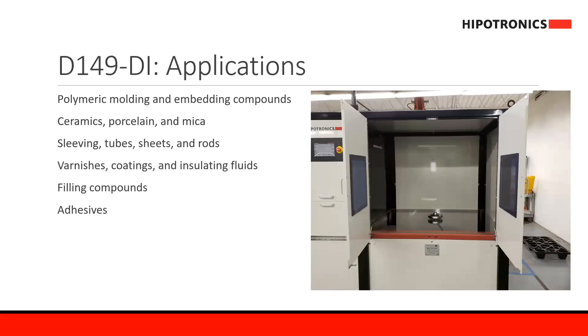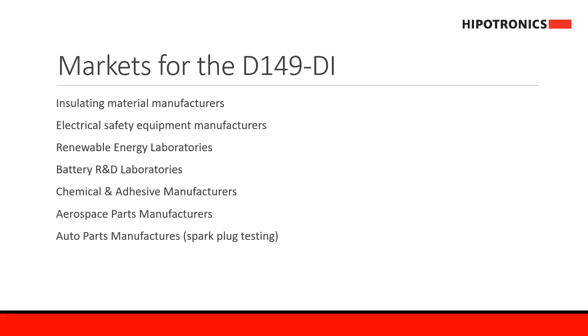The D149 DI series can be used to test polymeric moldings, embedding compounds, ceramics, tubes, sheets, rods, varnishes, coatings, adhesives, or any filling compounds — essentially any type of insulating material for electrical testing. The D149 DI is usually seen in insulating material and electrical safety equipment manufacturers, as well as in laboratories for renewable energy and battery research and development. Chemical and adhesive manufacturers, as well as aerospace and auto parts manufacturers, also use this type of system.